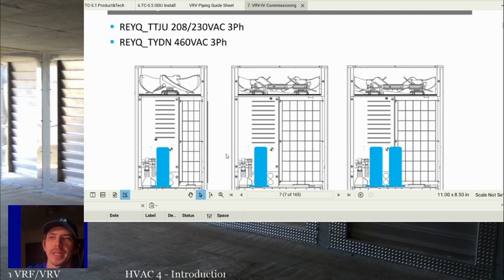And that makes heat recovery capable of doing heating and cooling simultaneously. So a heat pump can only provide heating or cooling. The whole system has to be running in heating, or the whole system has to be running in cooling. On heat recovery, you can run simultaneous heat and cooling, except for on very hot days when you probably wouldn't need heating anyway. Your discharge line that would run to your indoor units to provide heating is now switched over as an extra suction line to carry the additional load in the building. So that's the difference. That's the primary difference between heat pump and heat recovery. When you see the piping sizes, what you'll find is the liquid line is the smallest line.